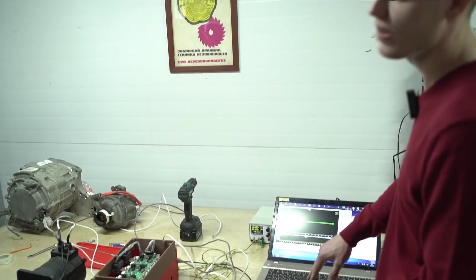So it does have some torque, right? Yeah, there's some torque, but I need to overload it to tell, and its RPMs are low. Low RPM, I can't precisely tell you the exact number right now, but it's also a multi-pole motor, meaning it has multiple magnetic poles. So right now it's probably operating at approximately 870 revolutions per minute, essentially functioning like a 4-pole motor, based on its characteristics and design.